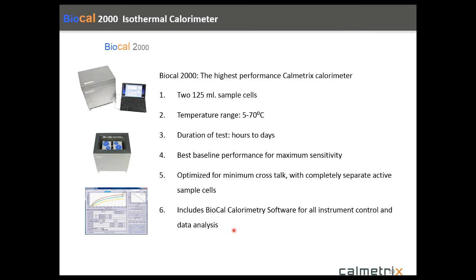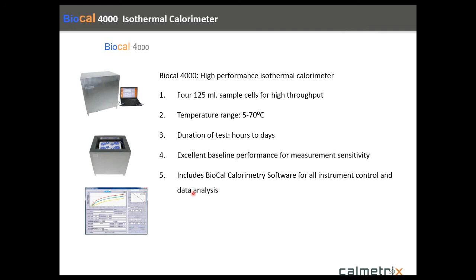The 4000 is considered our high performance calorimeter. Uses the same 125 milliliter sample cells and sample cups, but it has 4 samples, so you can run 4 simultaneously. So it has twice the throughput as the 2000, which might be important in many cases. Temperature range the same, duration of test the same. Very excellent baseline performance. In most situations that we're dealing with, it's going to be perfectly suitable in terms of the application. It includes the software and computer, just like the 2000. So those are the 2 different instruments that are available.